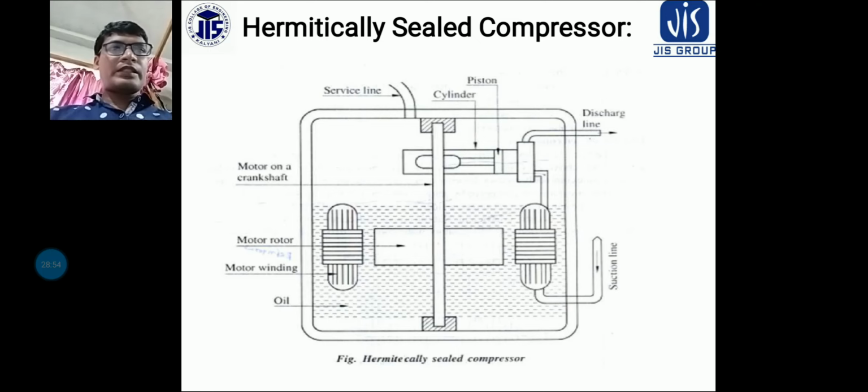that means alternating current AC electric supply, and that too of the voltage and frequency the particular assembly is designed for. In the event of motor burnout, highly corrosive hydrochloric and hydrofluoric acids are formed due to disintegration of the fluorocarbon refrigerant, that is R12, R22, R11, which are the refrigerants we are using here, at the high temperature associated with a motor burnout.